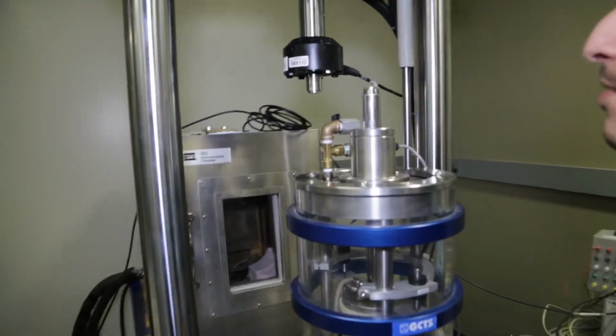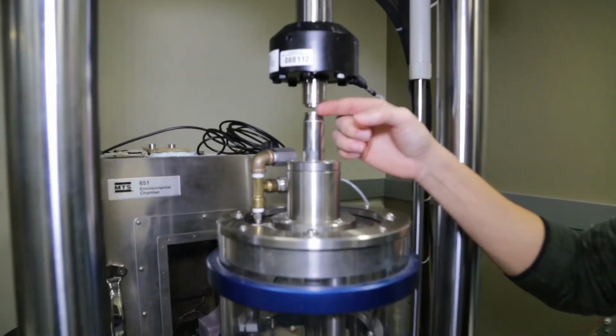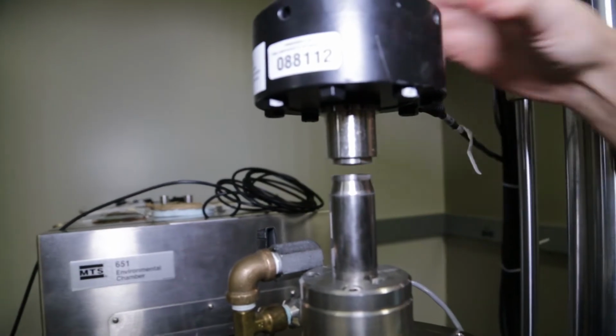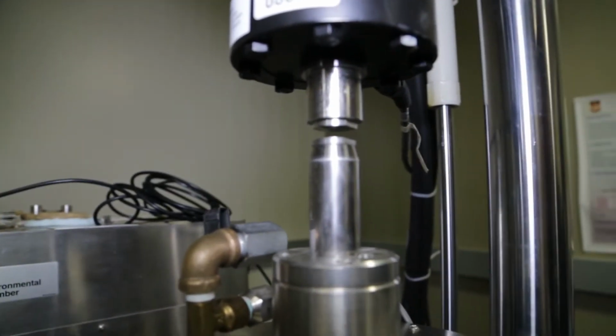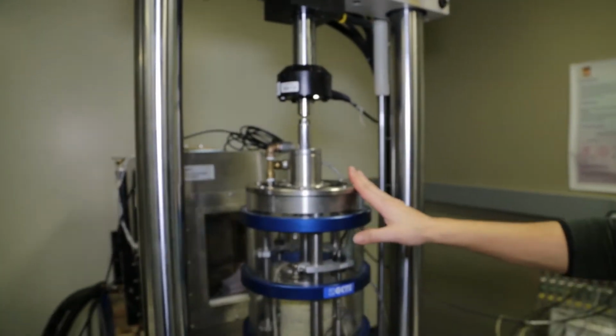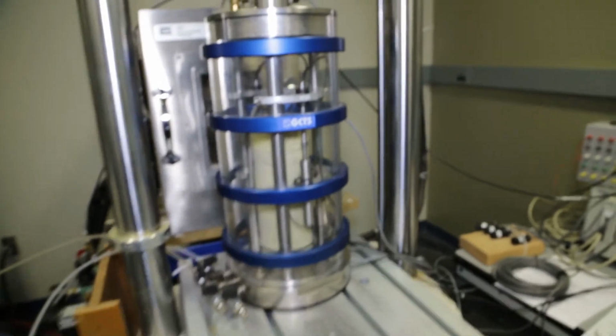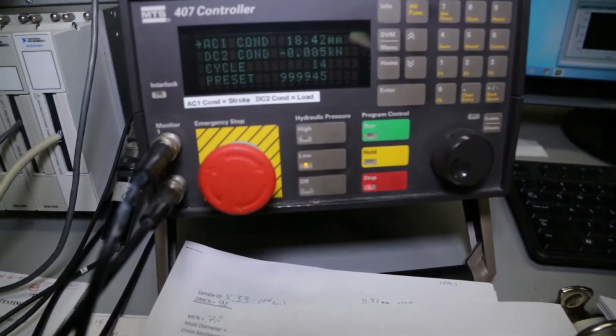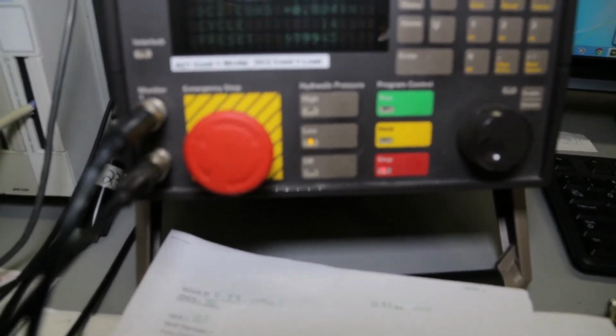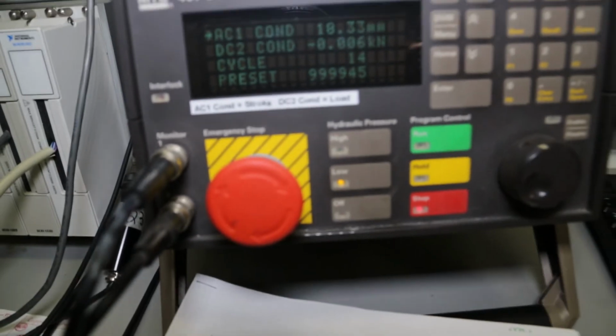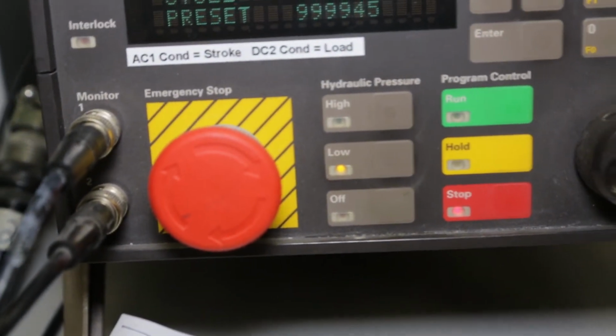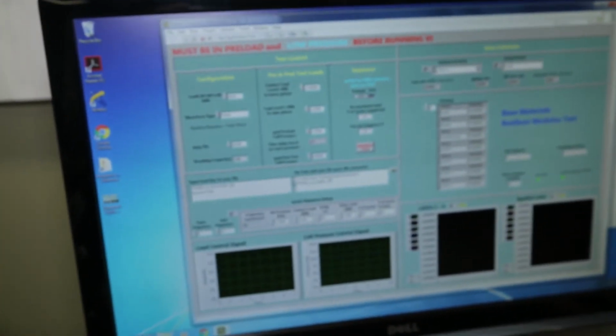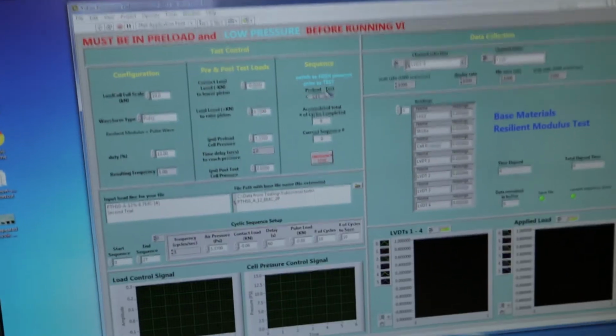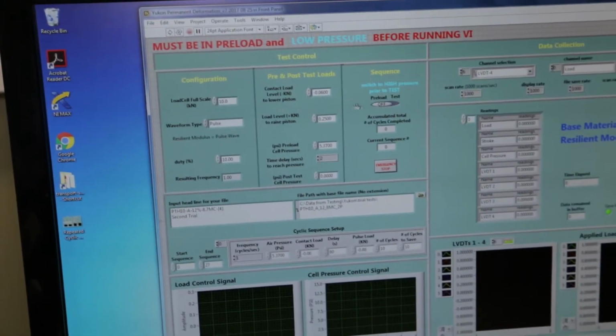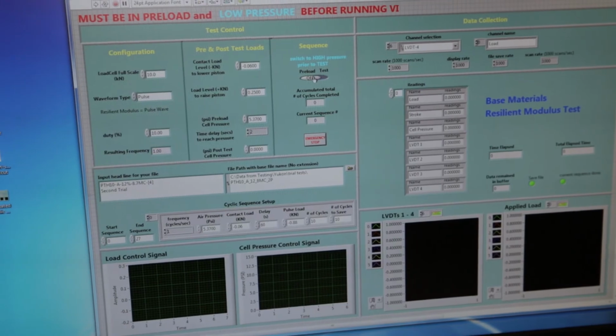Now since it's high enough, push the sample under it, make sure it's aligned. After I make sure it's aligned, I make sure it's on low pressure here on the control. And I double check my connections again, and I make sure I entered the right data on the testing program. Make sure I have the naming done right so that it doesn't overwrite another sample. And before I click run, I make sure that the setting is on preload, not testing.